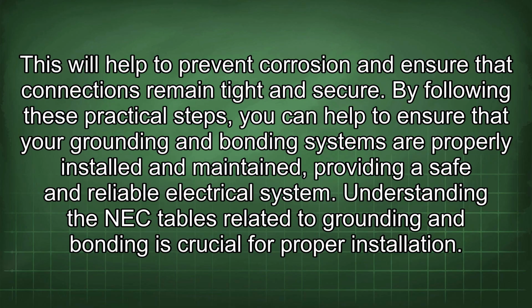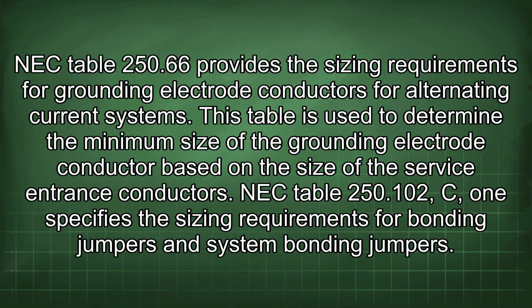By following these practical steps, you can help to ensure that your grounding and bonding systems are properly installed and maintained, providing a safe and reliable electrical system. Understanding the NEC tables related to grounding and bonding is crucial for proper installation. NEC Table 250.66 provides the sizing requirements for grounding electrode conductors for alternating current systems. This table is used to determine the minimum size of the grounding electrode conductor based on the size of the service entrance conductors.